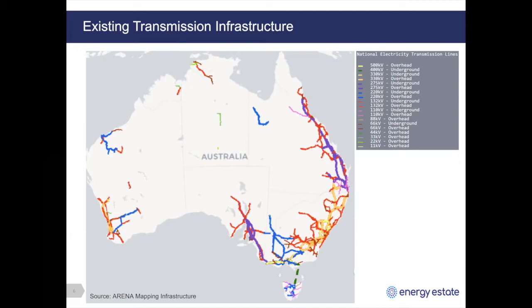For offshore wind, you might be 30 or 40 kilometres offshore with the additional costs of operating offshore, but you would connect directly into a key grid node — a very different situation than doing a one-gigawatt onshore project, which may have fantastic resource but be far from infrastructure. The blue line from Victoria into New South Wales to Broken Hill had plans for a one-gigawatt wind farm, scaled down to 200 megawatts and currently constrained much of the time. That's one key reason why offshore wind will play a major part in Australia.